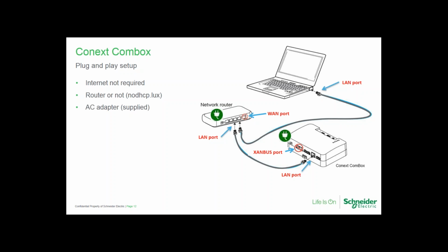So before, it was necessary to call tech support, and they would set the customers up with what we call the Conext Config Tool, which is a dongle that connects between your laptop and the device in question, and then you could recover it that way by just selecting the right firmware file and downloading it. We have since corrected that with the ComBox, to where they have a program that will allow recovery of a bricked unit using the ComBox. So that's a great feature.